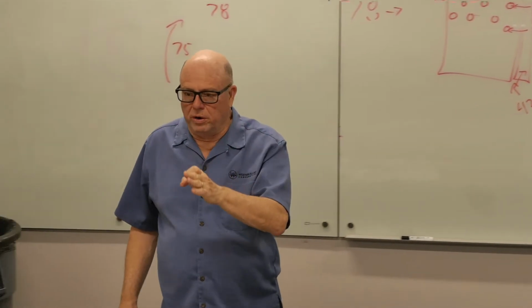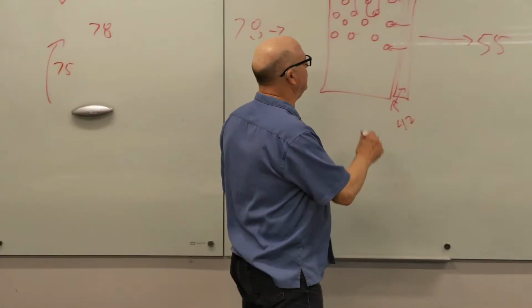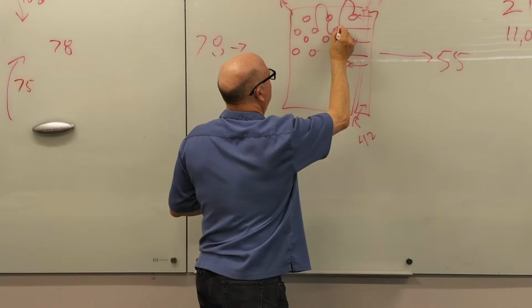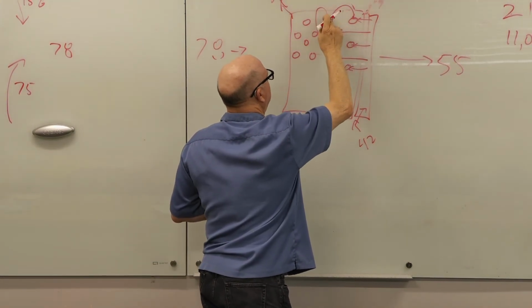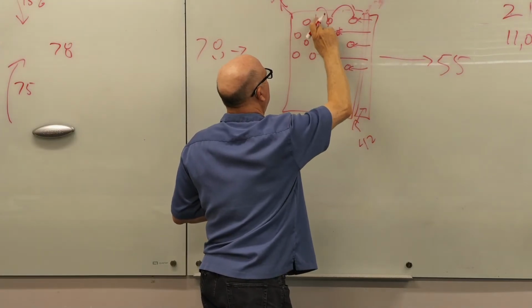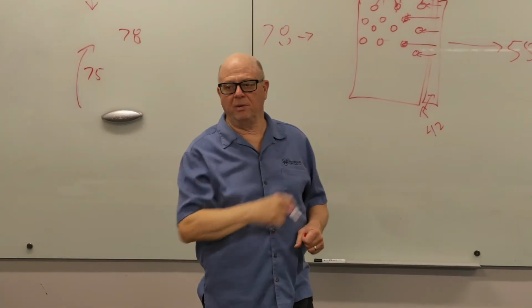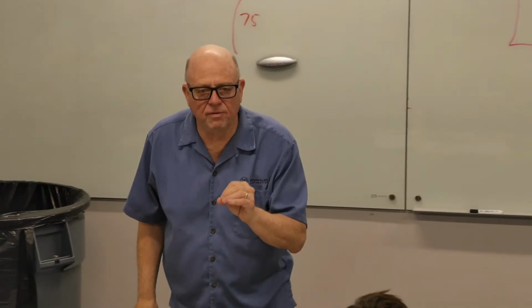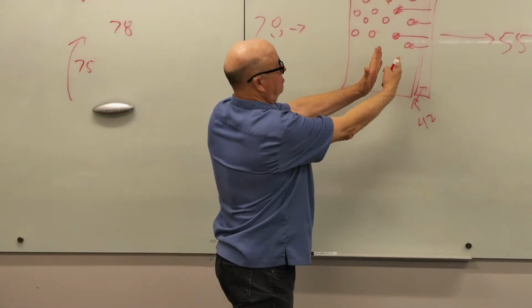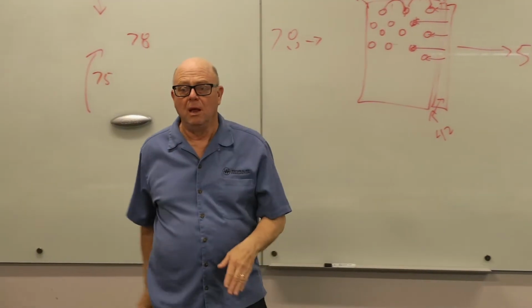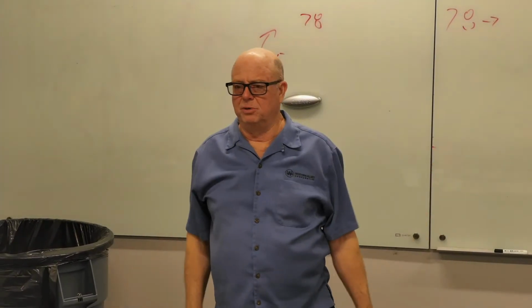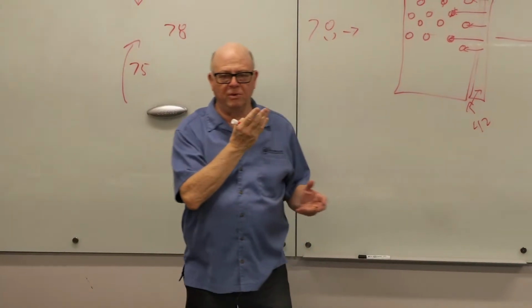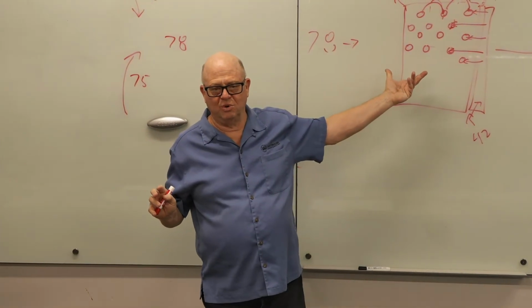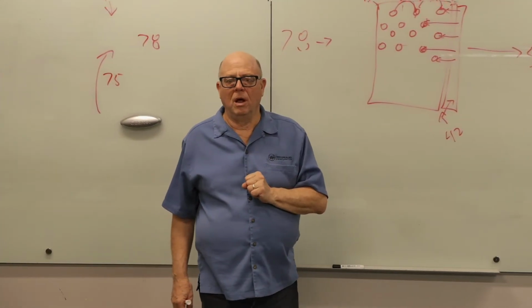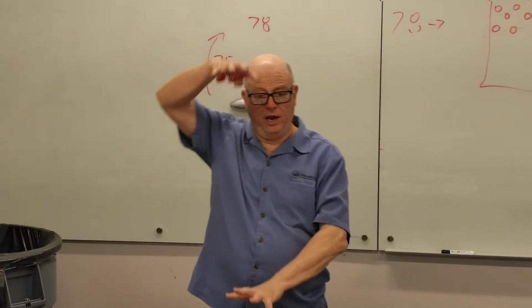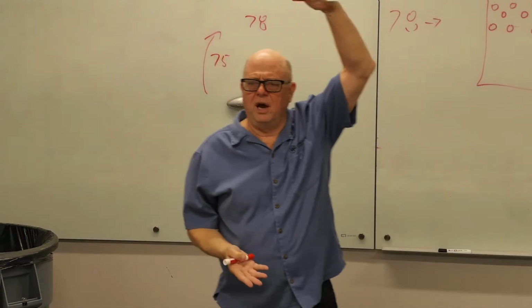If we really got to make this air cold, we might have to go to a double circuit. And then we're feeding the front 2 rows. And so this one goes then to here. And this one goes to here. And the same thing below it. The penalty you get for that, because now we're putting 42-degree water in the last third of the coil if it's 6 rows, right? The penalty for that is you can't get the high rise on the water temperature. You just can't, because it's not exposed to the air as much. It's only making 3 passes to get through a 6-row coil. On the other hand, let's say your priority was that you wanted a high rise. Why would you want a really high rise?